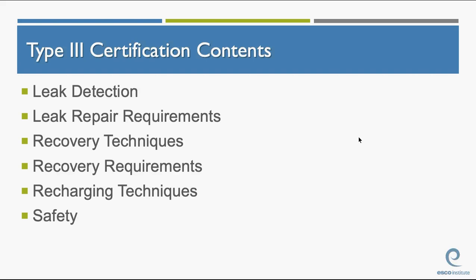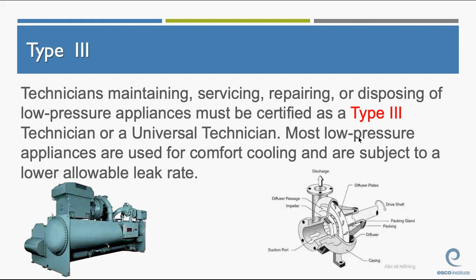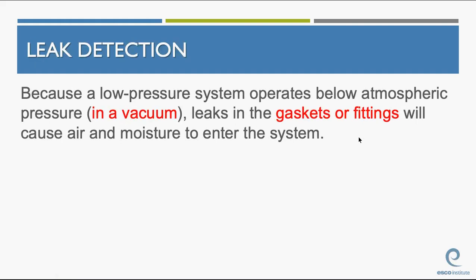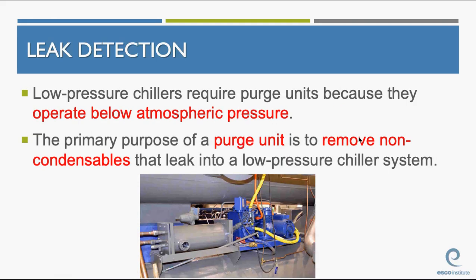So you will do fine with Type 3 if you remember our primary concern is that non-condensables and moisture leak into the system, and we're working in a vacuum. Again, technicians maintaining, servicing, repairing, or disposing of low-pressure appliances must be certified as a Type 3 technician or universal technician. Most low-pressure appliances are used for comfort cooling, and they're subject to a lower allowable leak rate. Because a low-pressure system operates below atmospheric pressure, it operates in a vacuum. Leaks in the gaskets or fittings will cause air and moisture to enter the system. That's what I said earlier. Low pressure, we're worried about leaks entering the system.